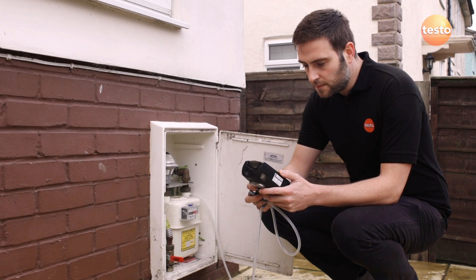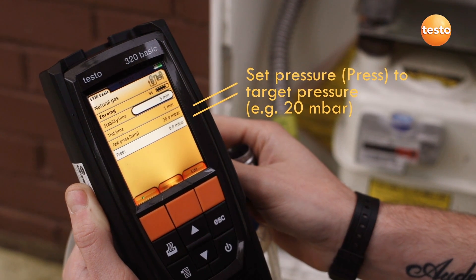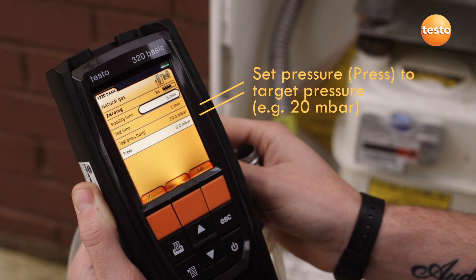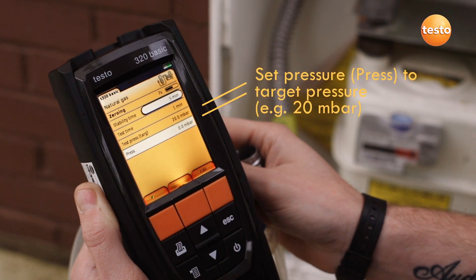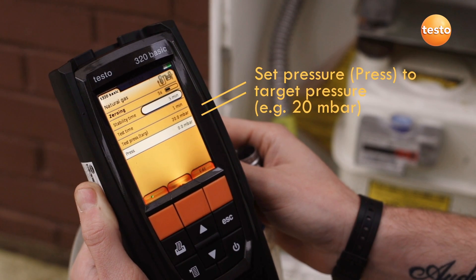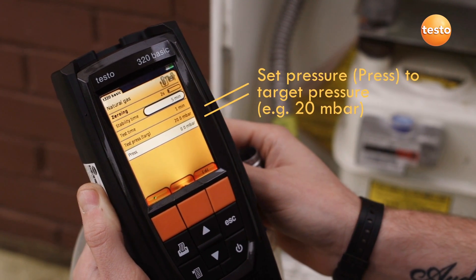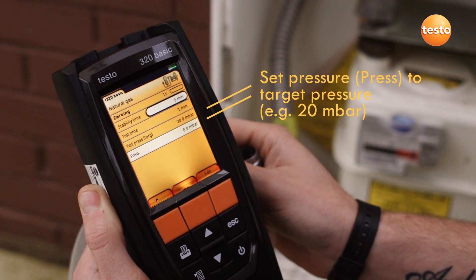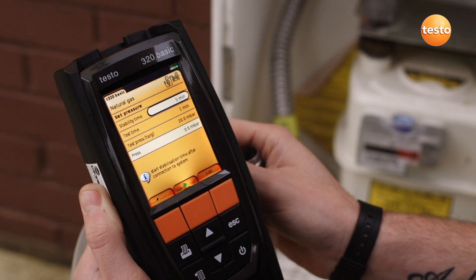After zeroing, the 320B displays the tightness test with default settings which can be adjusted. In this case, the target pressure is 20 mB and the test is to check that the pressure doesn't drop, which would indicate a gas leak.